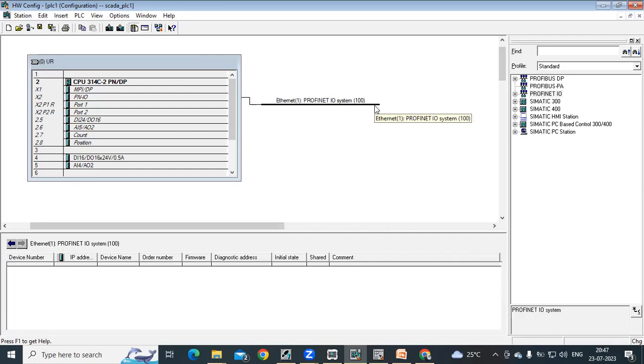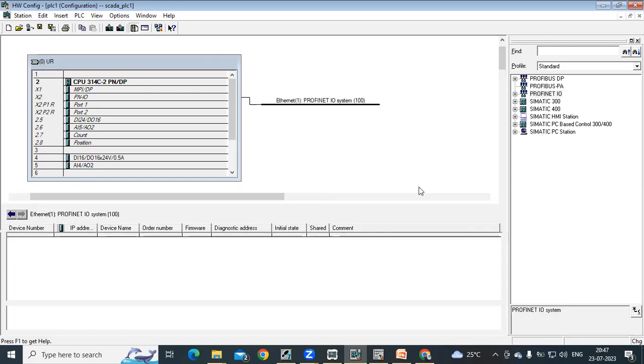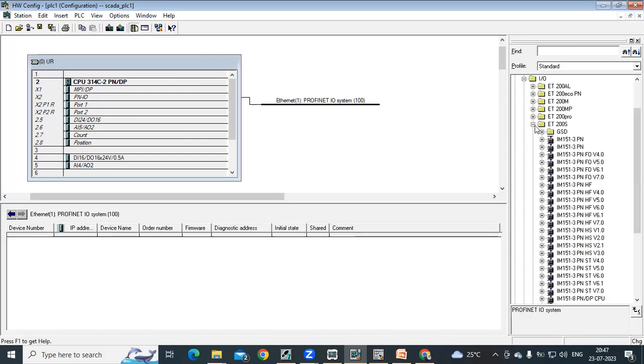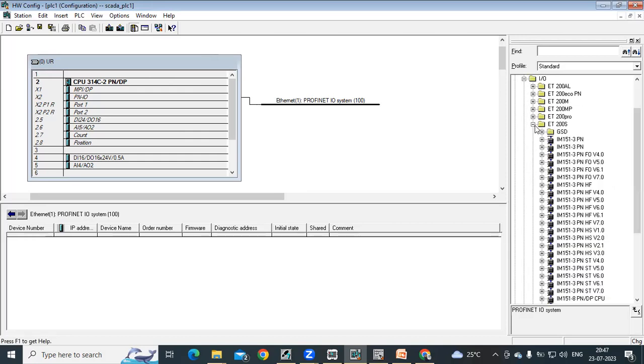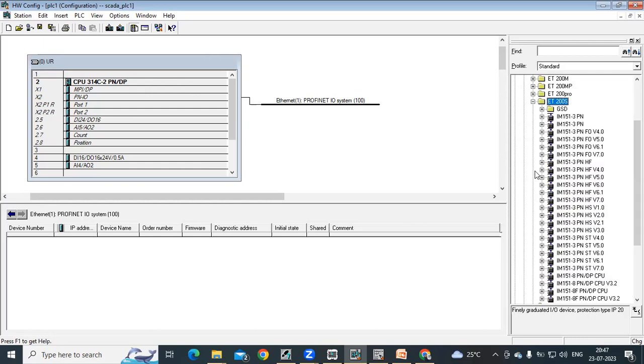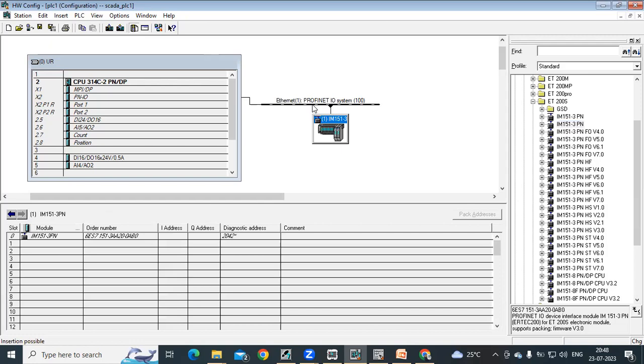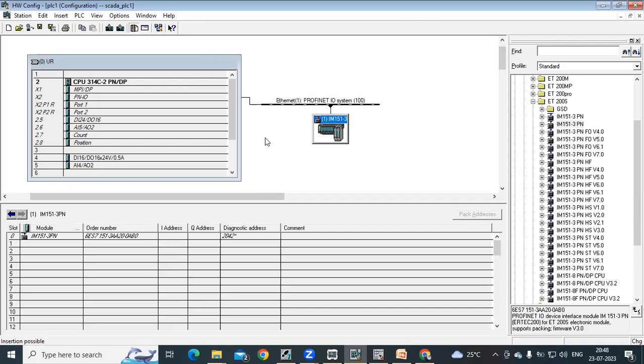What we need to do is add our IOM. We are having different IOM modules. From catalog, select the Profinet IO, expand this Profinet IO, go to the ET 200S option. When you expand this folder, you can see different types of modules. If you are using ET 200S with terminal, expand this. We are having different IOM modules, so I take one basic one, IM 151-3 PN. Just drag this and drop it on your profile. Now this is added here.